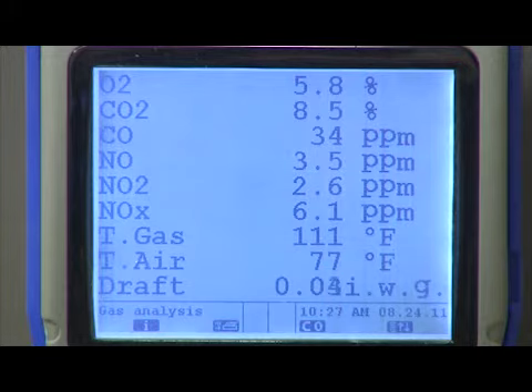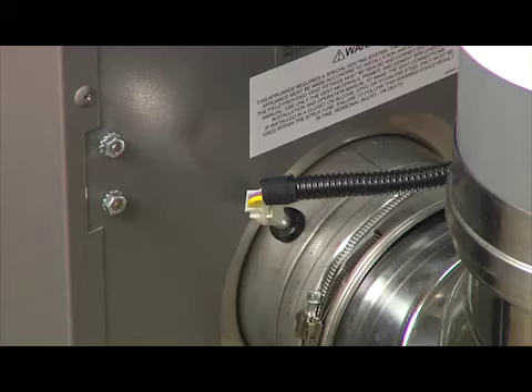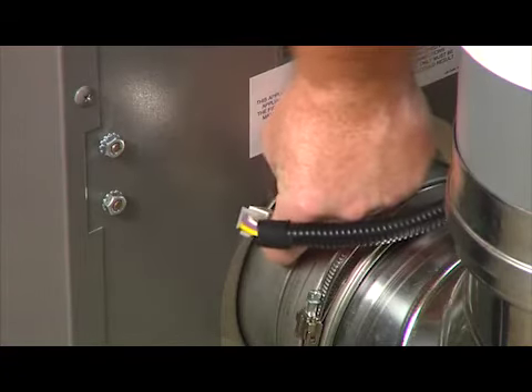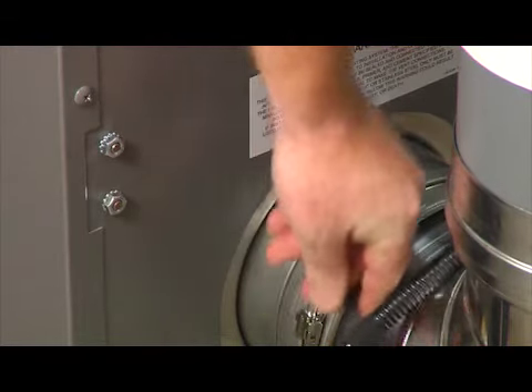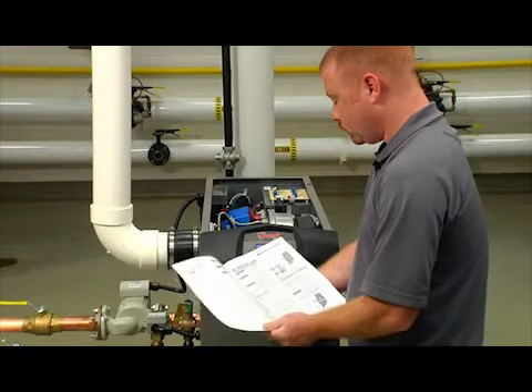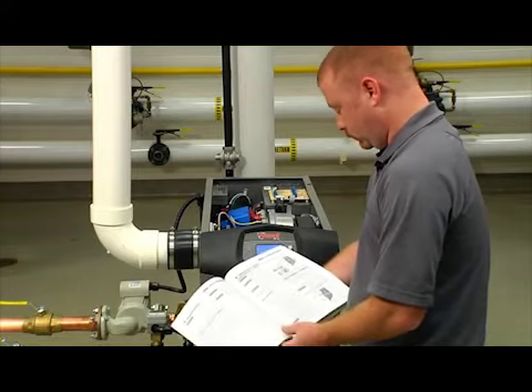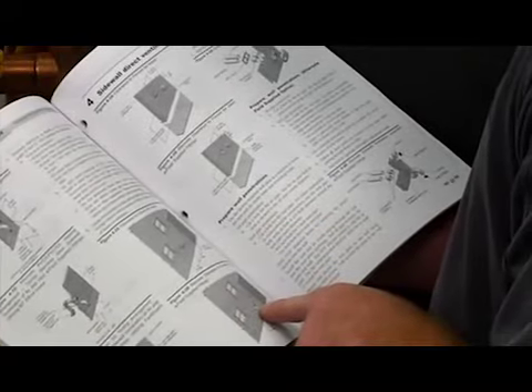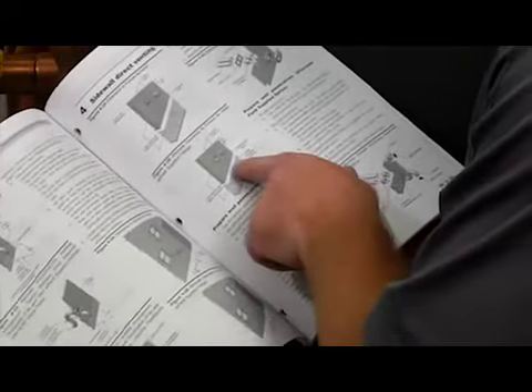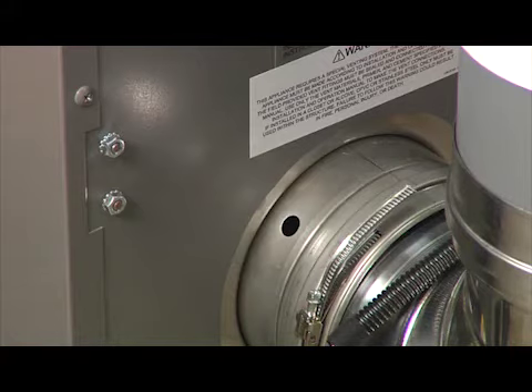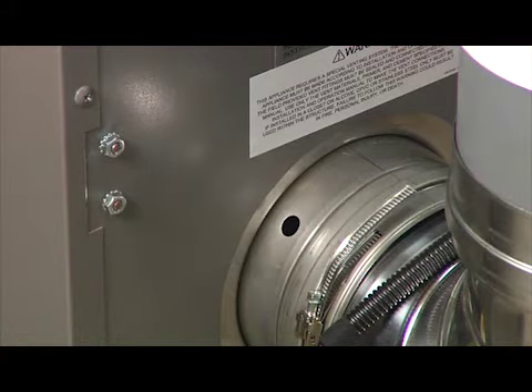If the CO2 and CO levels are not within the specified ranges, several items could be the cause. Verify that the vent and air intake pipes are installed correctly. Reference the venting section of the installation and operation manual that was supplied with the unit for the proper installation methods. Verify that there is no blockage or obstruction in the vent or air intake pipes or at the terminal points.